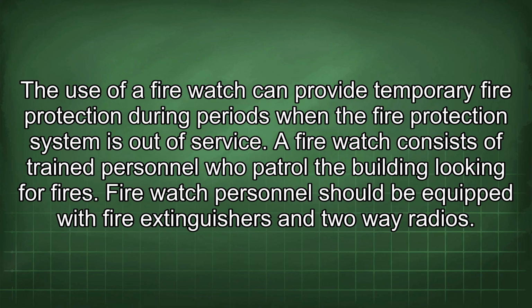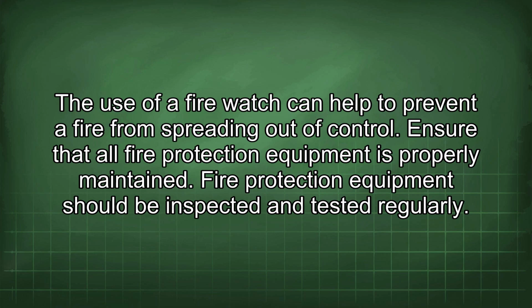The use of a fire watch can provide temporary fire protection during periods when the fire protection system is out of service. A fire watch consists of trained personnel who patrol the building looking for fires. Fire watch personnel should be equipped with fire extinguishers and two-way radios. The use of a fire watch can help to prevent a fire from spreading out of control.